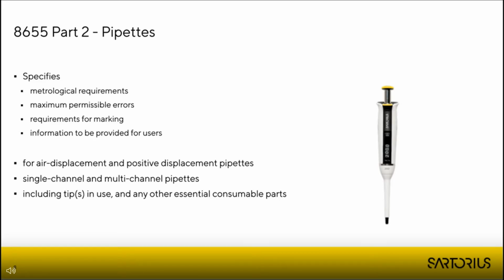Then requirements for markings. So here in the picture you see that there's a manufacturer name, there's a brand name, and there's a volume. So those are just a couple of examples of what you need to have in pipettes, that they need to be permanent. And then information to be provided for users. When you bring a new pipette to market, you need to have a certain set of information, like how to use it, how to clean it, how to decontaminate, so how to take care of it, as well as a recommendation for calibration.